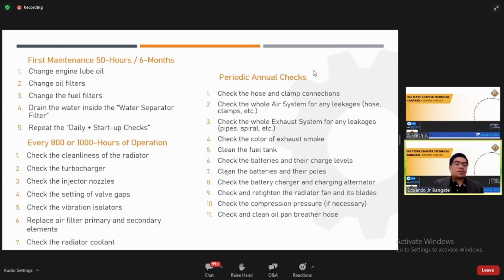Okay, so what about the first maintenance at 50 hours, 6 months? You have to change the engine oil, the engine lube oil, change oil filters, change the fuel filters, drain the water inside the water separator filter, and repeat the daily startup check. But sir, the engine oil is still clear. Why should we change it? The oil filter is still clean, why should we change it? This is a requirement from the manufacturer. If you don't follow it, the manufacturer studied this and determined it needs to be done.